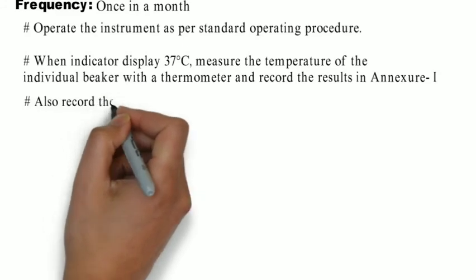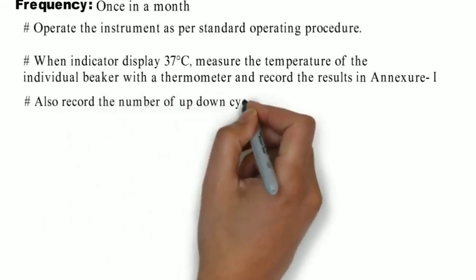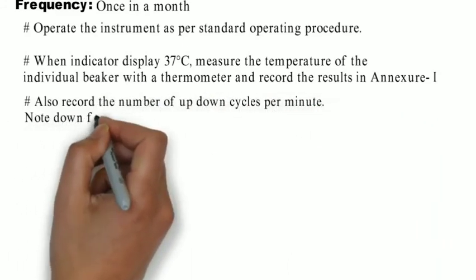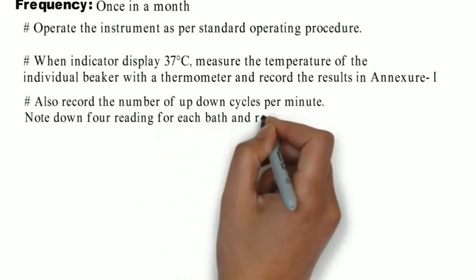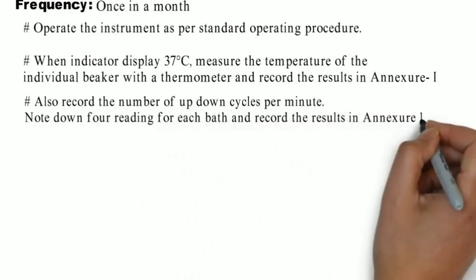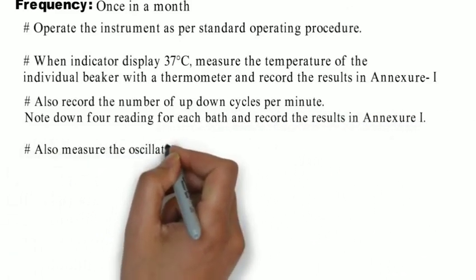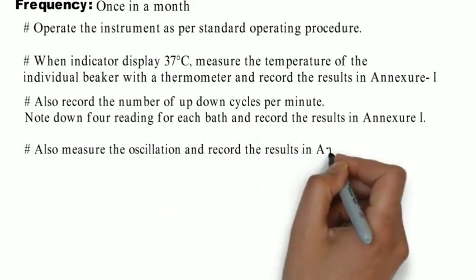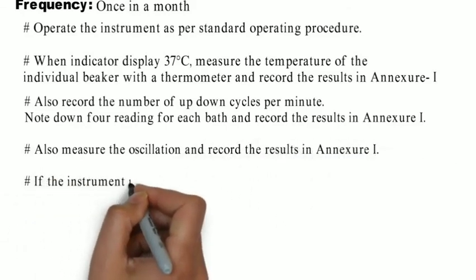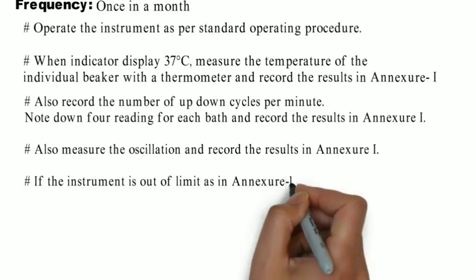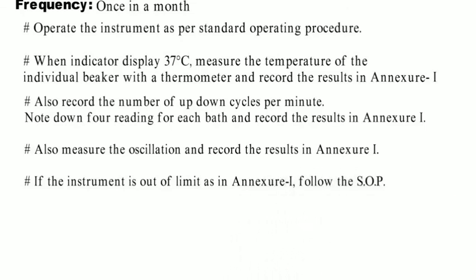Also record the number of up-down cycles per minute. Note down 4 readings for each bath and record the results in annexure 1. Also measure oscillation and record the results in annexure 1. If the instrument is out of limit as per annexure 1, then we have to follow the SOP. Whenever our instruments do not meet the limits in annexure 1, we have to follow the SOP.